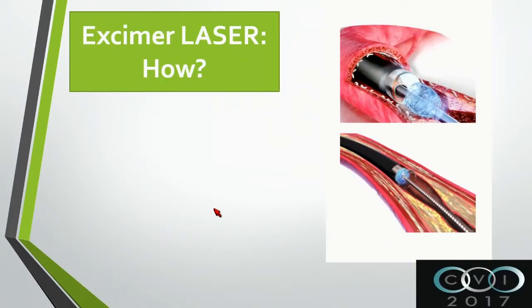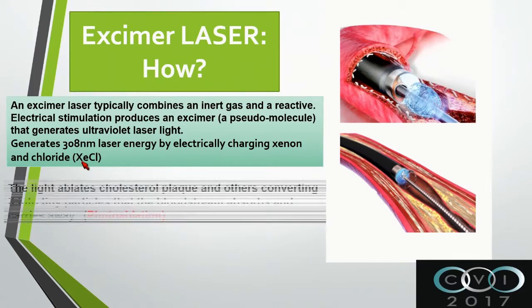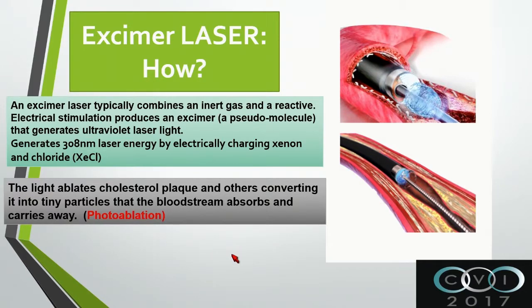This is an example of the laser that's used. The excimer laser typically combines an inert gas and produces a reaction. The electrical stimulation produces what we call an excimer, which is a pseudomolecule that generates ultraviolet laser light. This ultraviolet laser light goes at about 300 nanometers and electrically charges the xenon and chloride. The light ablates the cholesterol - we call it photoablation. So instead of mechanically removing the plaque, we are doing photoablation.